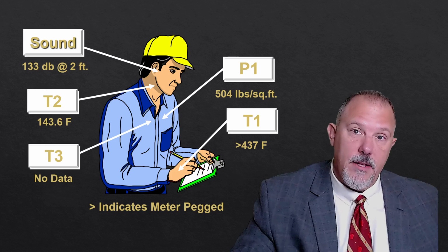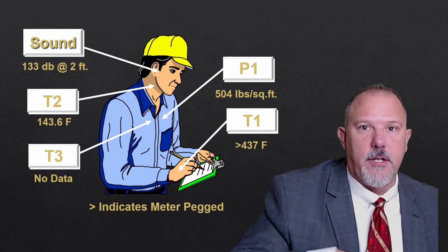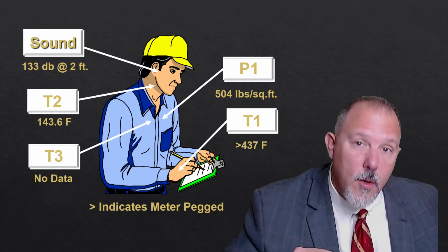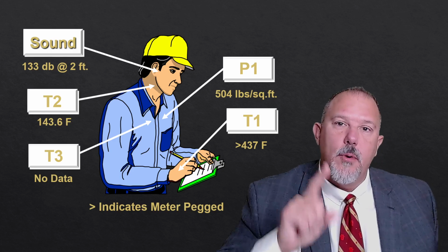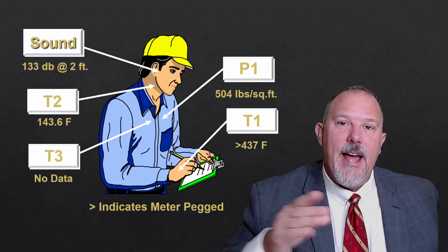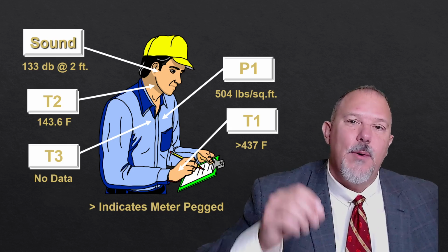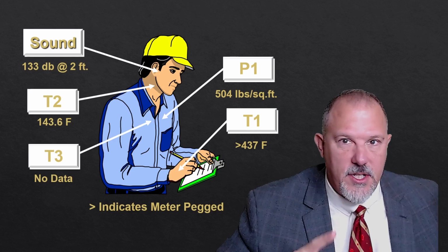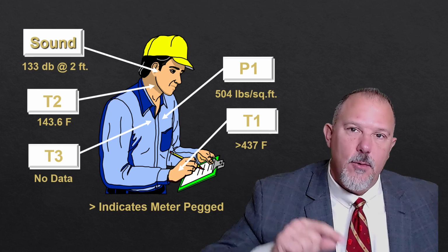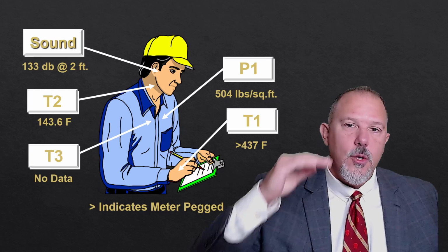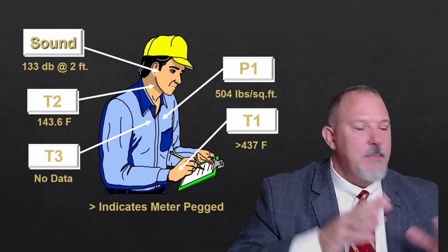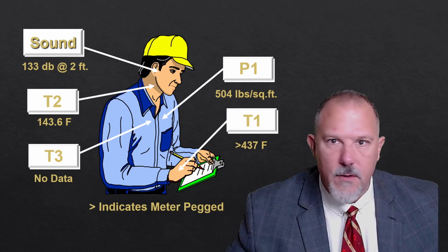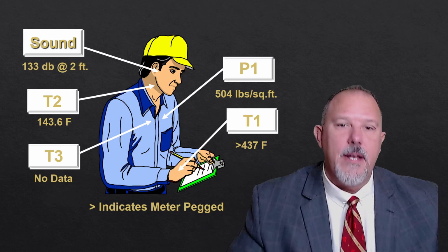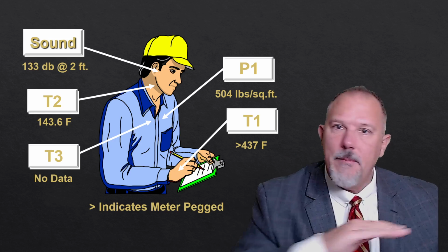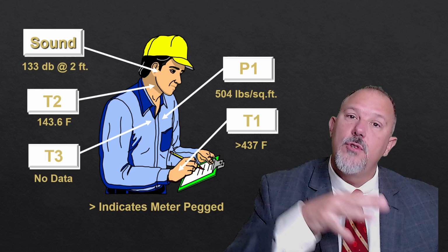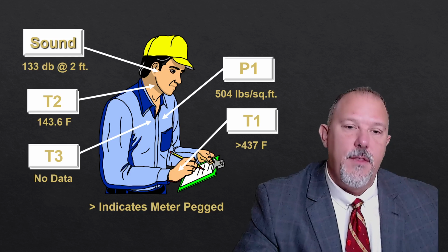Now, the next event has an even faster clearing time. This is less than a quarter cycle. Now, what is one cycle? 0.016. A half a cycle is 0.008 seconds. A quarter cycle is 0.004 seconds. So as I reduce the clearing time, same event, same available fault current, same type of equipment, I'm reducing the clearing time only. Hence, I am reducing the severity of the event.